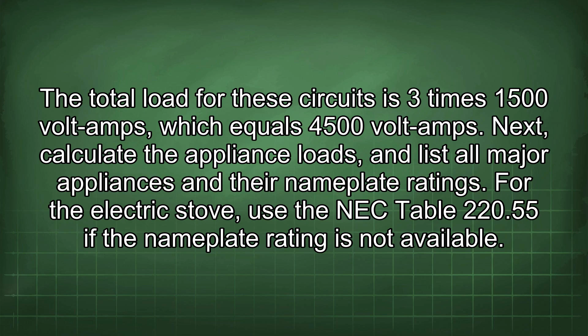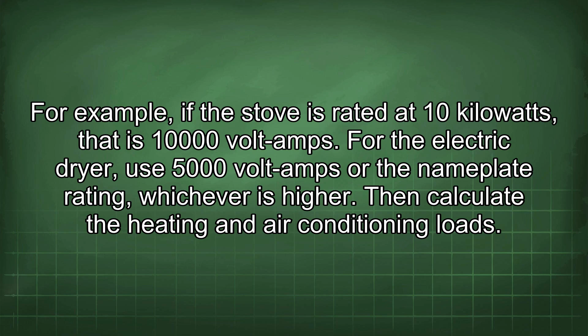For the electric stove, use the NEC table 220.55 if the nameplate rating is not available. For example, if the stove is rated at 10 kilowatts, that is 10,000 volt amps. For the electric dryer, use 5,000 volt amps or the nameplate rating, whichever is higher. Then calculate the heating and air conditioning loads.